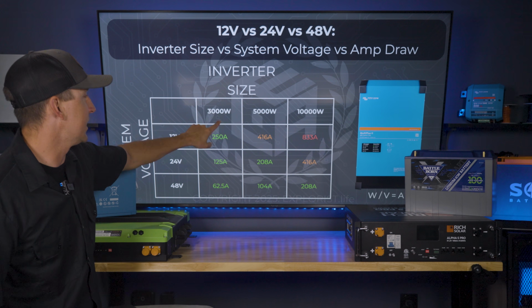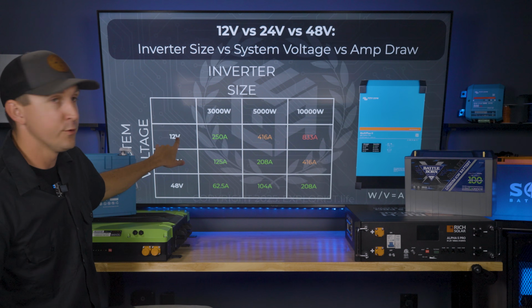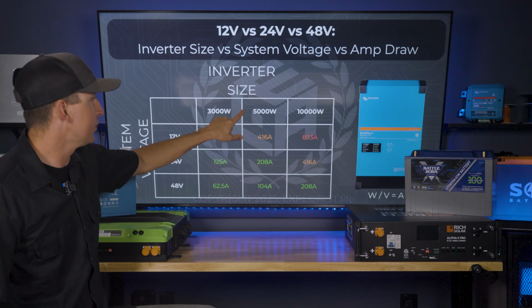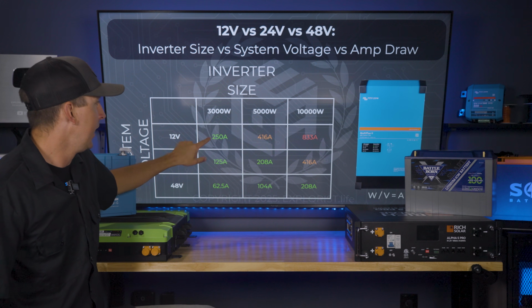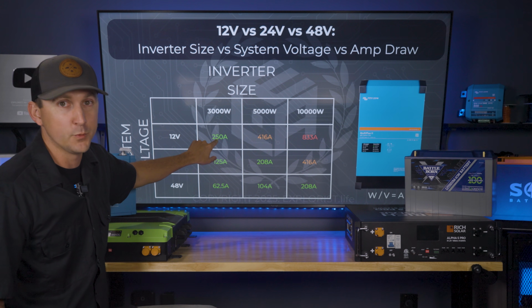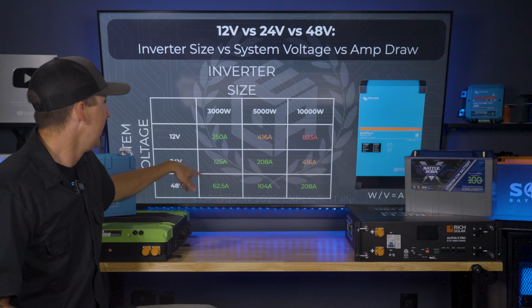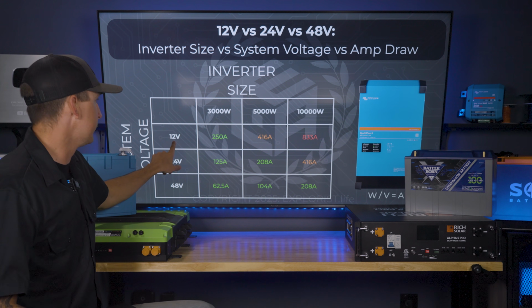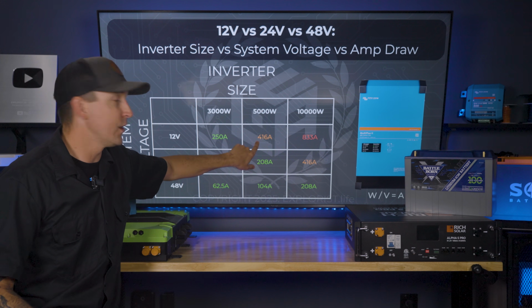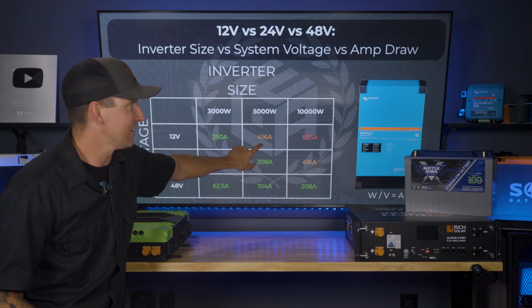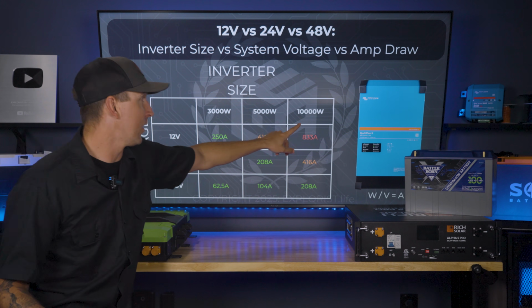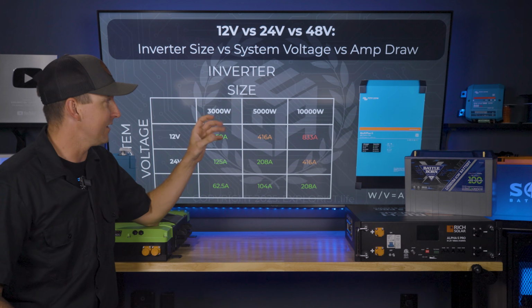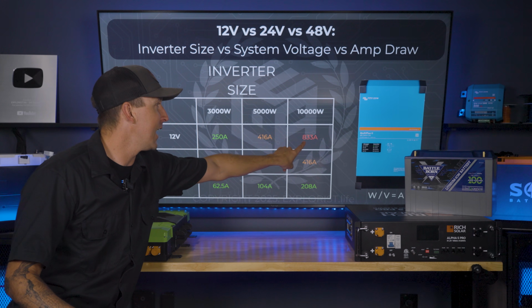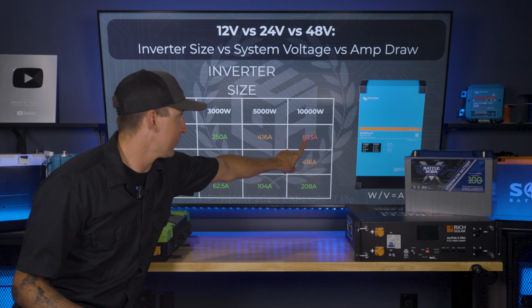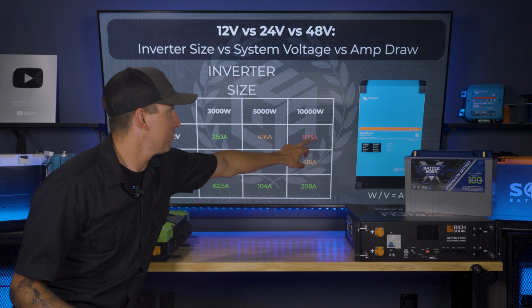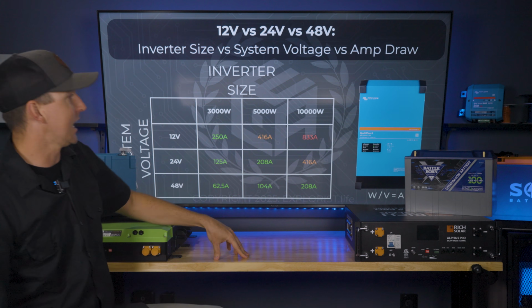If we had an inverter size that was 3,000 watts and it was running at 12 volts, it's going to be pulling 250 amps whenever it's operating at full capacity. If we had a 5,000 watt 12 volt inverter, that's going to be pulling 416 amps, and that's a lot of power. Now if we had a 10,000 watt inverter operating at 12 volts, I don't know that that exists, because of how bad of an idea it would be to be trying to pull 833 amps from a battery bank. That's probably why Victron doesn't even make that size.